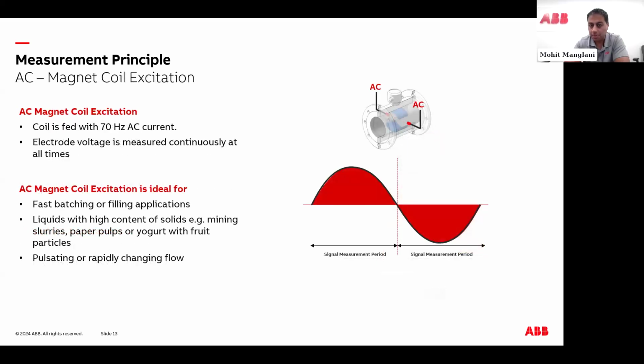And this is a picture of your AC magnet coil excitation. Basically, this is the type of power we're putting into the magnetic field so that you can get an accurate reading. I would say 95% of the meters we push into the market are DC powered, and they're more than capable of handling pretty much every application a normal mag meter can handle. AC meters we typically see in heavier slurries, heavier solids, heavier viscosities, or even super low conductivities. So that's where the position is on deciding whether you want to go with a DC or an AC meter.